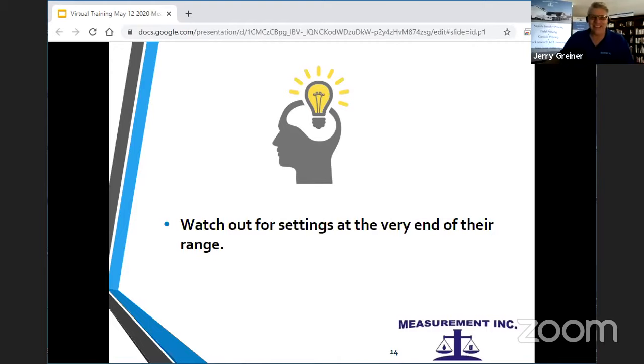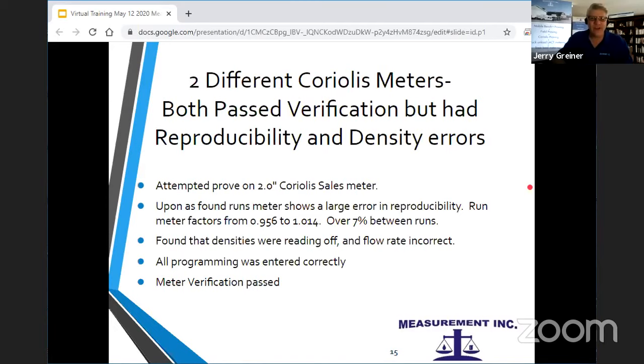Okay, next is we have 2 different Coriolis meters. They both had similar issues when we found it. We attempted the first one that we're going to talk about. Let's see, I don't have a picture of the first one, but it's a 2-inch Coriolis sales meter, and the as found runs showed a large error in reproducibility. The run meter factors went from 0.95 to 1.014 or something, so about 7% difference between runs.